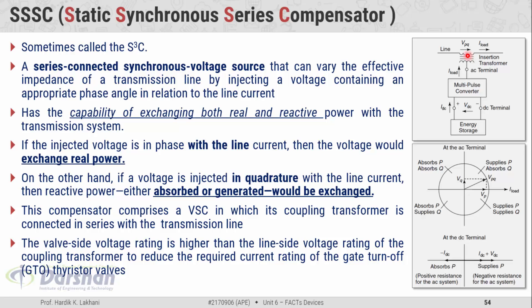The valve side voltage rating is higher than the line side voltage rating of the coupling transformer to reduce the required current rating of the gate turn-off thyristor valves. There are two windings of this coupling transformer — the primary winding is in series with the line, and the secondary winding is where the multi-pulse converter and the energy storage devices are connected. The voltage rating on the secondary side is kept higher to keep the current in that branch at minimum magnitude, so that we can reduce the current ratings of the gate turn-off thyristors in the voltage source converter. It is a basic concept that on whichever side of a transformer the voltage magnitude is higher, the current magnitude would be lower.